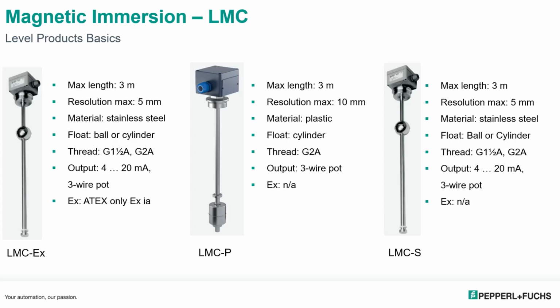Like the LMLs, we have 3 different versions of the LMCs. The EX version, the maximum length is 3 meters. Like I said, there are reed switches all along that rod, and the resolution of this LMC-EX is about 5 millimeters. So every 5 millimeters, there is a reed switch with a resistive network on it. It can come in stainless steel. You can get the floats as ball or cylinder. We show the threads here, G1.5 or G2, but they also come with NPT, and you can get them with flanges, ANSI or DIN style. The outputs are 4 to 20 milliamp or 3-wire potentiometer, and this particular one has an ATEX EXIA certification.